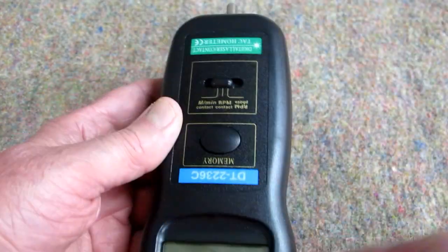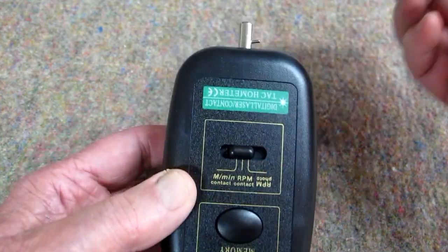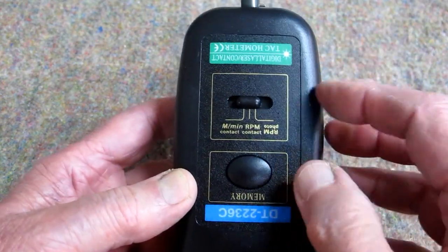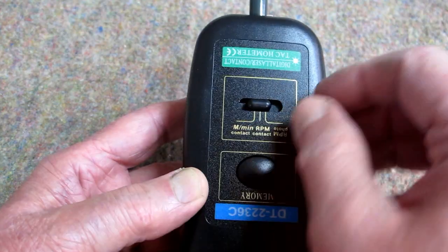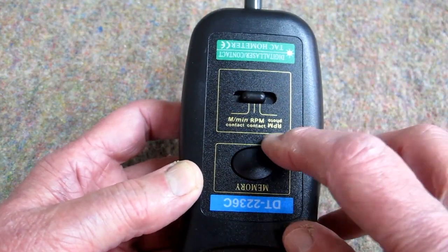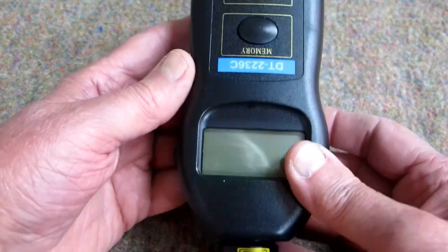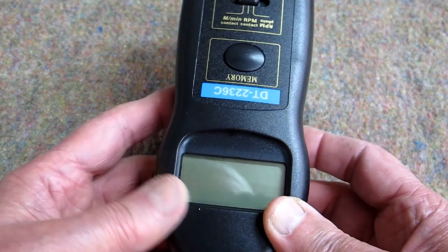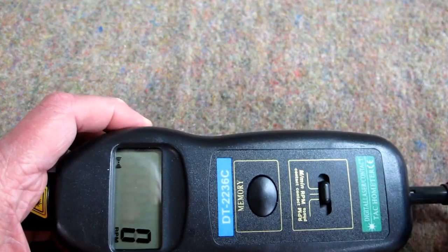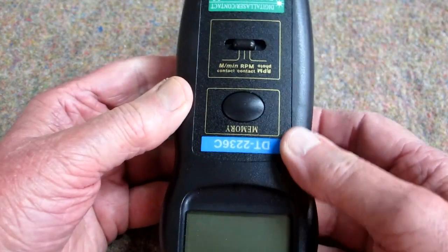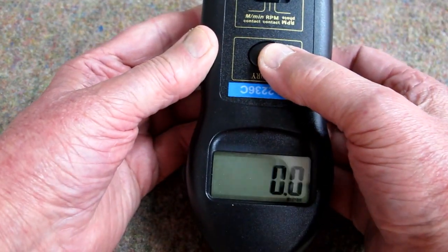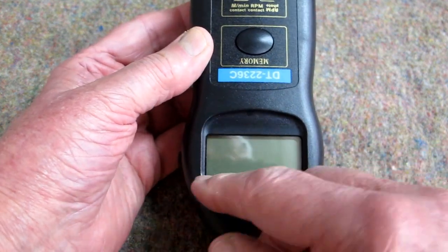If you want to do the contact tachometer, you put one of these pieces on here. And you slide the switch to the center position, which is contact RPM. And again, you have to push this button. When you're pushing that, this is turning and you let go of it. You come back and you push this and it will tell you what the RPM was. And this reads correctly in this position for the contact RPM.